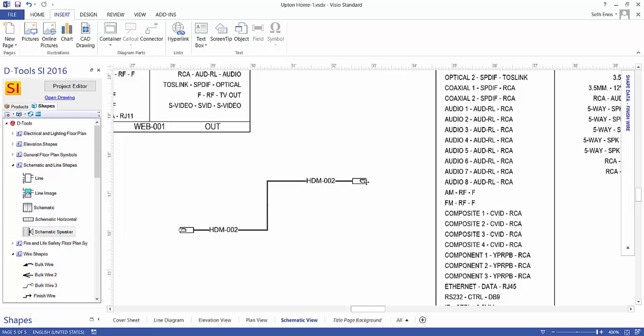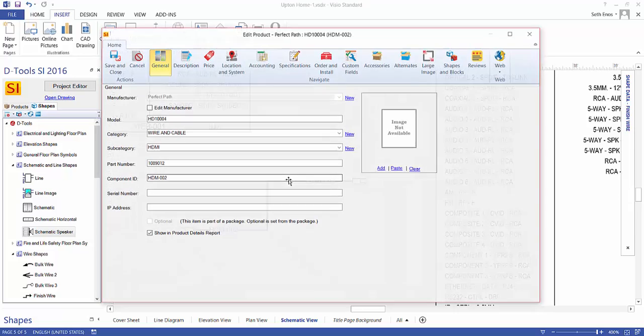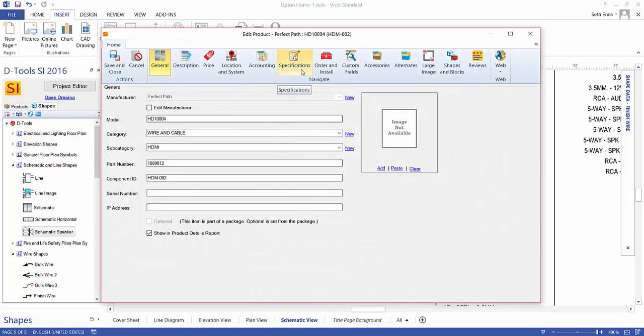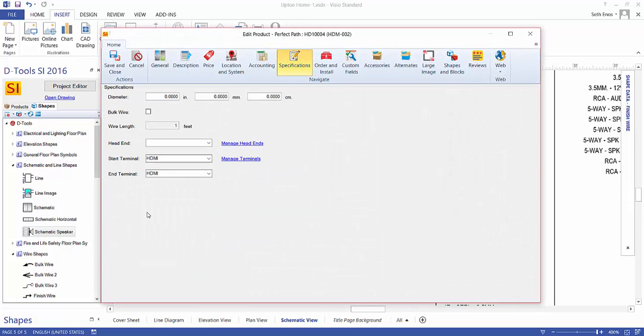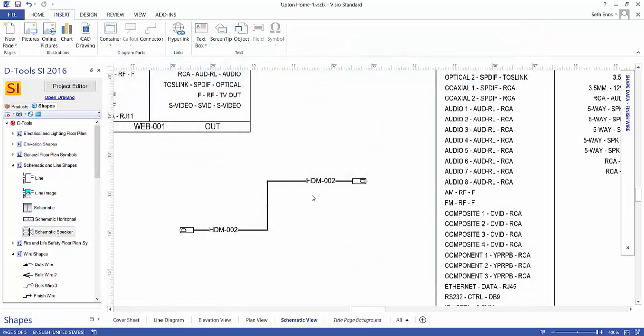The reason these ends are showing is that's a default setting in the software. It shows a graphic representation of the start terminal and end terminal that have been assigned to the wire. I'll double-click this to show you that. If you open up this wire and go to the specifications, you can see that a start terminal and an end terminal have been set, and for all of your major connections, there will be an icon representation as long as this field is entered for that wire.